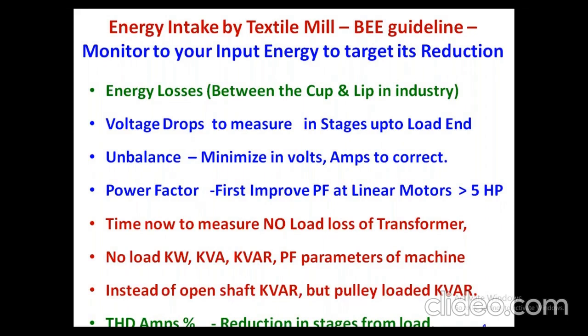If the VFD is fitted, it will maintain around 0.9 as the power factor. That is the best branded VFD. Why I am telling you this specifically: because some VFDs can give only 0.6 or 0.7. Some of the non-branded VFDs give around 0.7 or 0.8. It is not PF compensated. The branded VFD will always maintain a power factor of around 0.9. So the no load kVAR, kilowatt, kVA, kVAR of all these parameters will definitely help when we know whether it is the machine load or the yarn load. Basically, whether the machine is self-consuming more, or it is being used for the production of yarn.